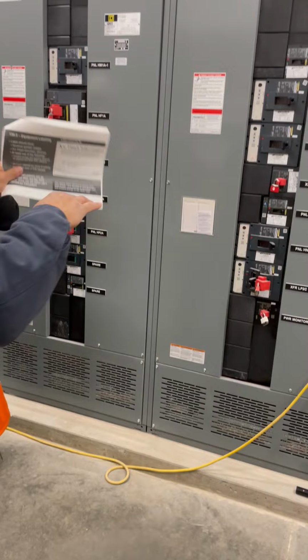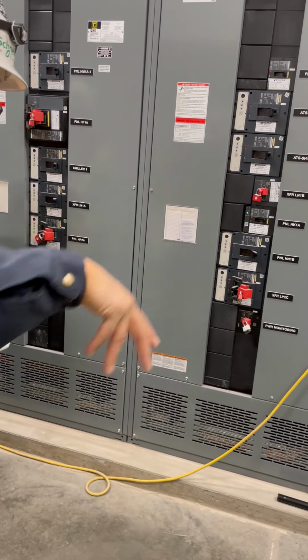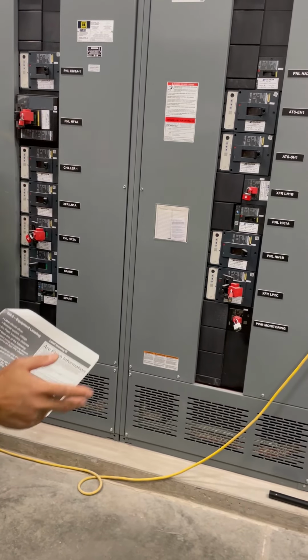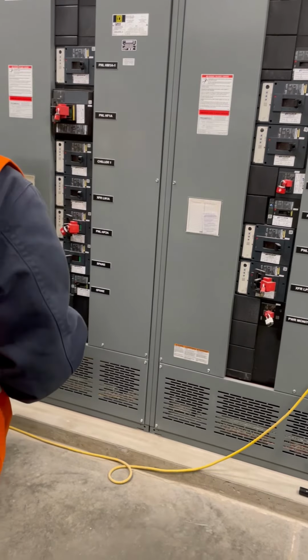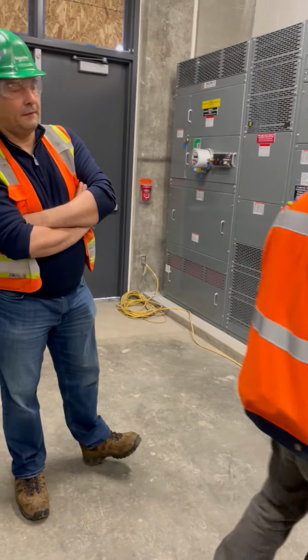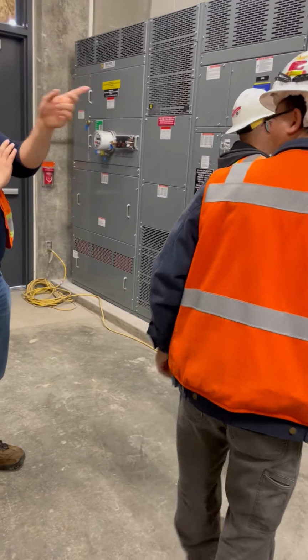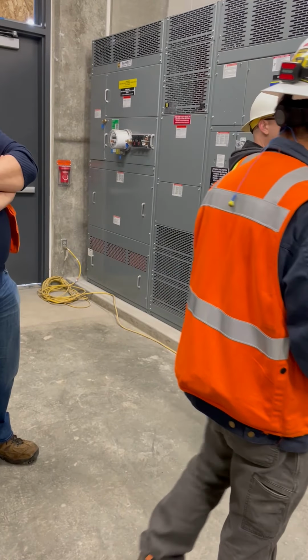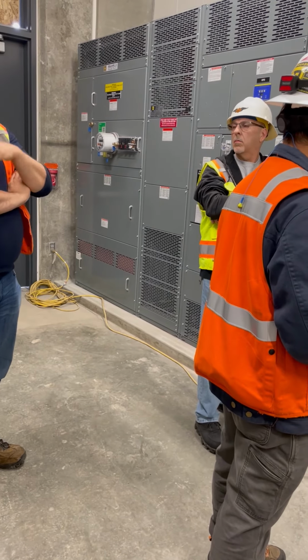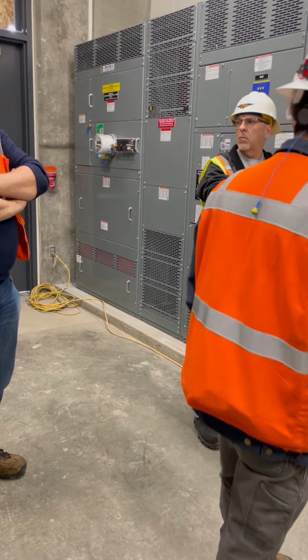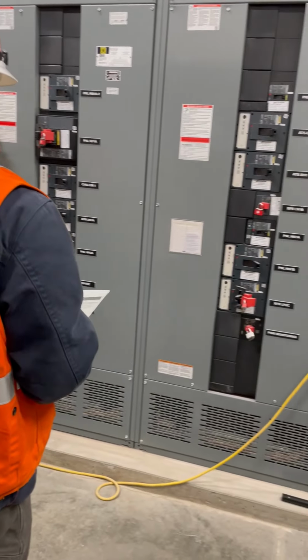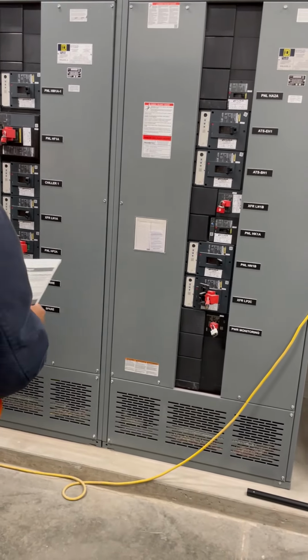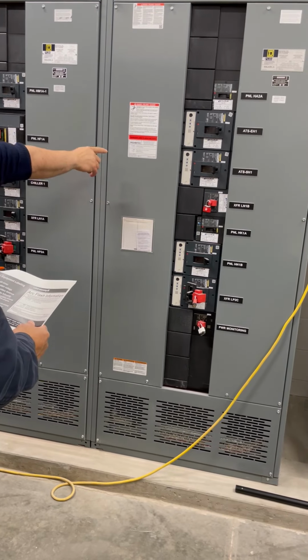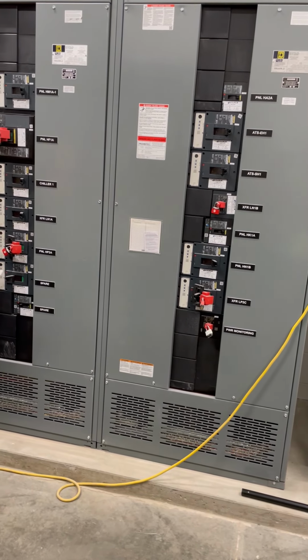When we did the calculation, it's like a sphere. We don't take into account a room and all that, because that's open air with no safety equipment on. Now, I think what that label will tell you is that you're not supposed to operate that switchboard even with safety equipment on, because the arc flash is much higher. That's why it says prohibited. So that's what the prohibited is for. Yes, 77 cal, which is very high.